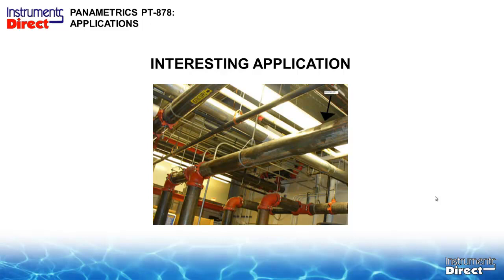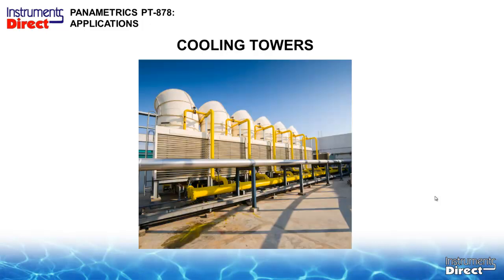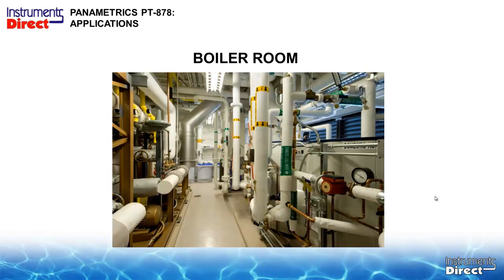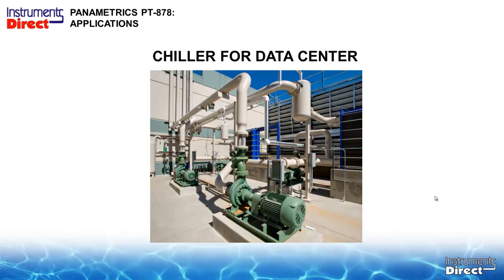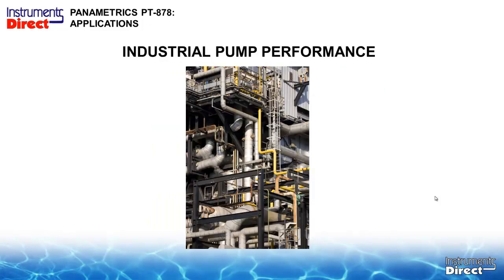So with something like that, we just talked about the 10 to 15 pipe diameters. This is considered a major disruption when you see these big connectors here. You're going to have to double your distance to go downstream to actually get the device to work.